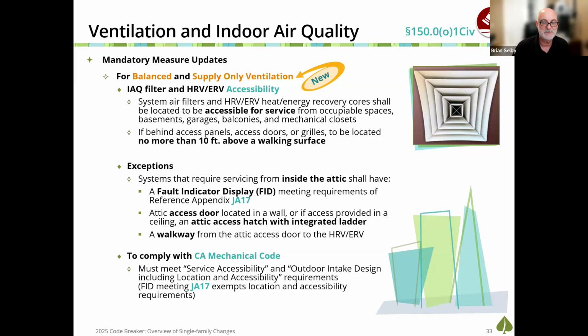So there are some exceptions for this. Put a fault indicator display inside, essentially meaning that there is something wrong with the filter system. If that filter is accessible from inside the attic, that is a very nice way to overcome accessibility issues. So additional exceptions apply when that filter is located in an attic behind an access door.